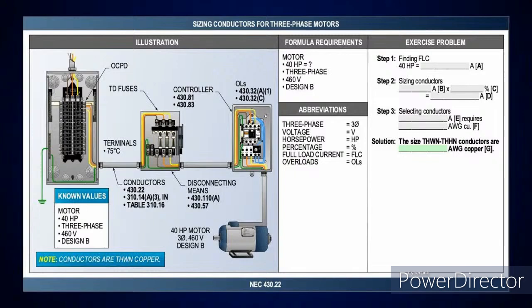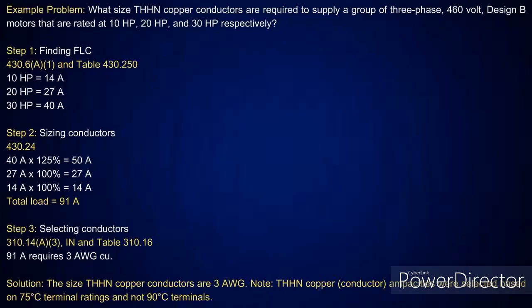And like in here, you've got a 40 horsepower, 3-phase, 460 volt design B motor. Where are you going to go? Table 430.250. Every time I'm sizing my conductor or overcurrent device, I'm at one of those tables. And then I only have a single motor, so 430.22 says I have to take it at least at what? 125%. Then you do that, you've got your amperage, then you go to table 310.16, find the next amperage size above it in the 75-degree C column, and there's your size conductor.